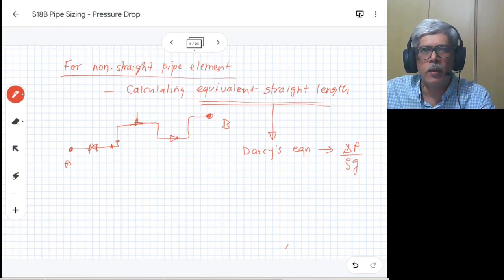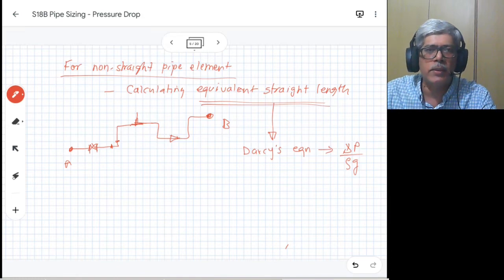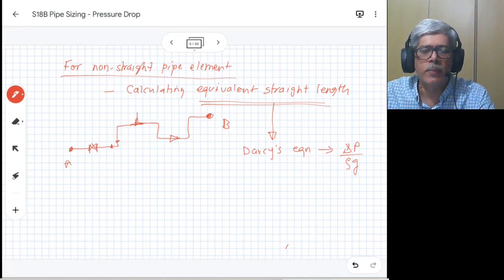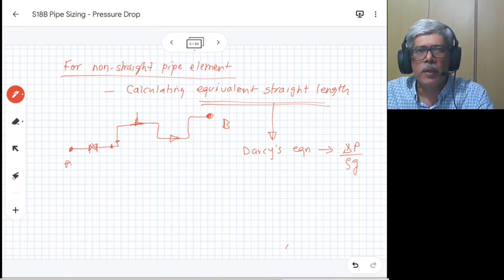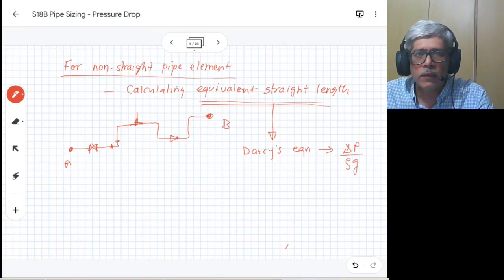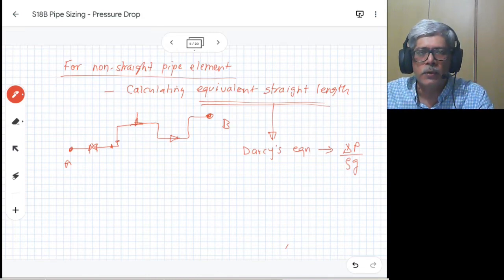So that is how this method works for sizing a pipeline from point A to point B. If you have a constraint on how much capacity of pump you can use, for a given pump size you have to determine what is the smallest pipeline size you can use. To reduce cost, you try to reduce the pipe size — the smaller the pipeline, the smaller the cost. However, a larger pipeline gives less pressure drop but higher cost, so some kind of optimum point needs to be found.